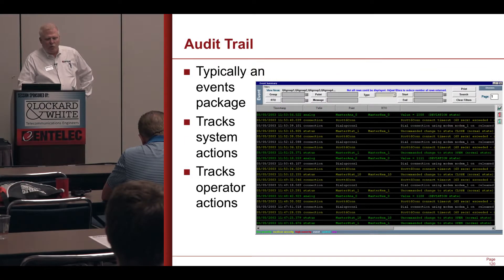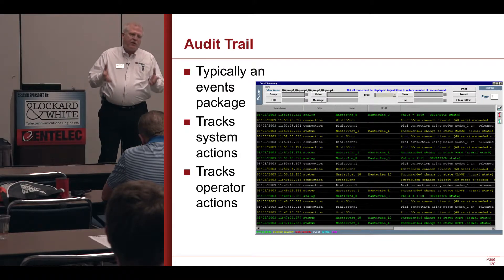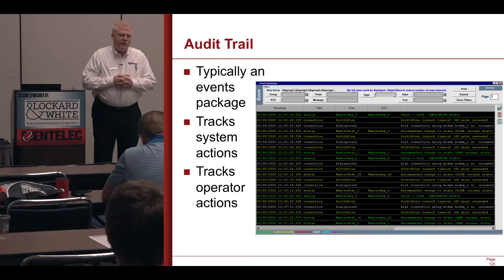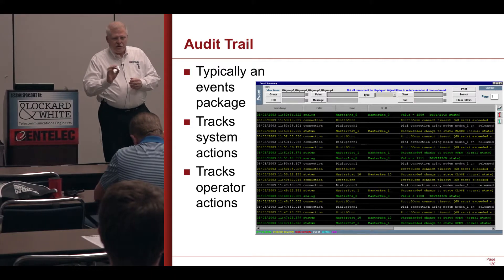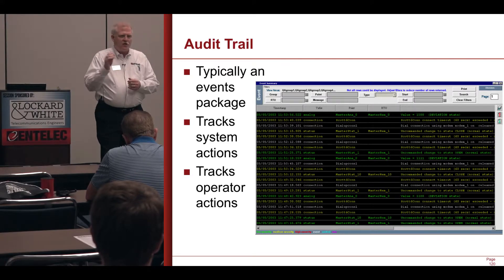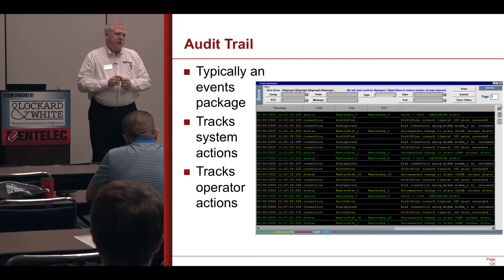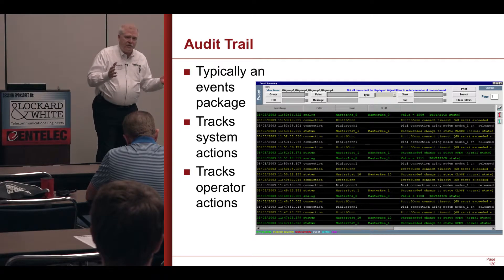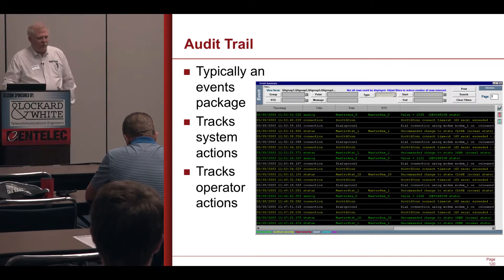You also want reports, and you need a full audit trail. If you're running a critical system and you have an incident, the accident investigators are going to want to see your audit trail. Note to self: if I'm in a regulated control room, I do not want login plans that are just console one, console two. It needs to be Joe Blow console one, Jack Smith console two — because the auditors, if there's ever an incident, are going to want to know who was on the desk, what were they doing, what was their workload, and how were they qualified.